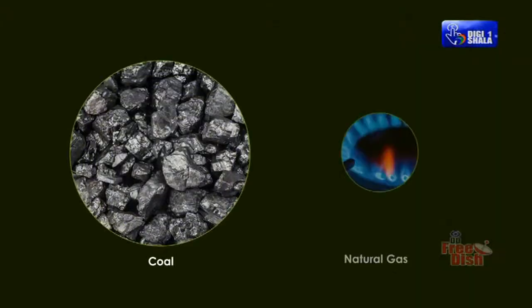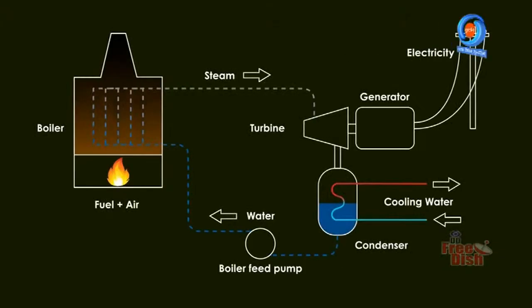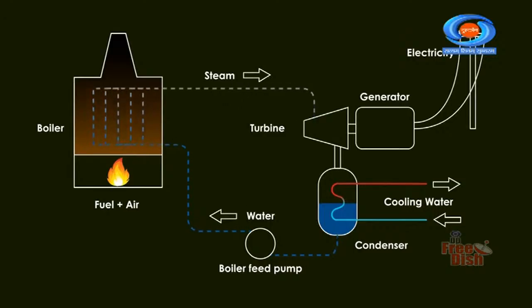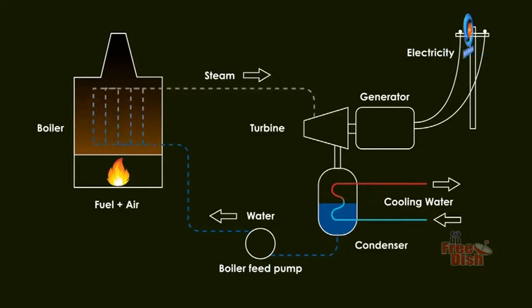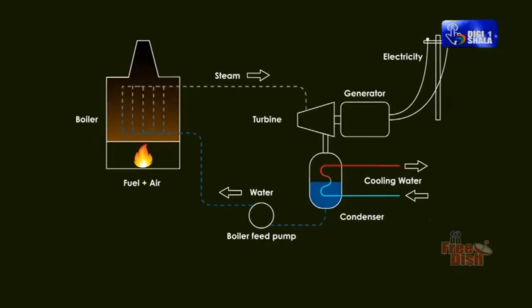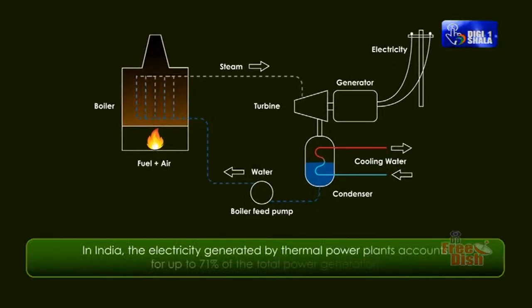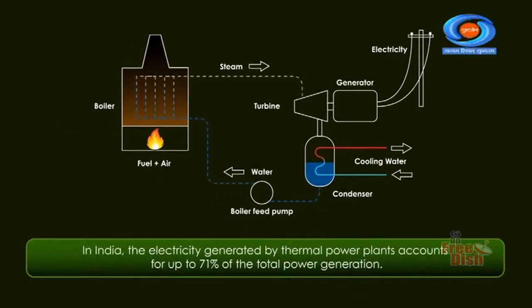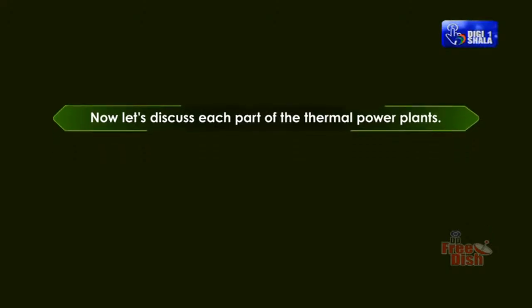Coal, natural gas or oil-fired boilers are used to heat water and generate steam. The steam is then used to turn a turbine which is connected to a generator that produces electricity. It is necessary to cool the steam after it leaves the turbine, condense it back into water and then circulate it through the system. In India, the electricity generated by thermal power plants accounts for up to 71% of the total power generation. Now let's discuss each part of the thermal power plants.